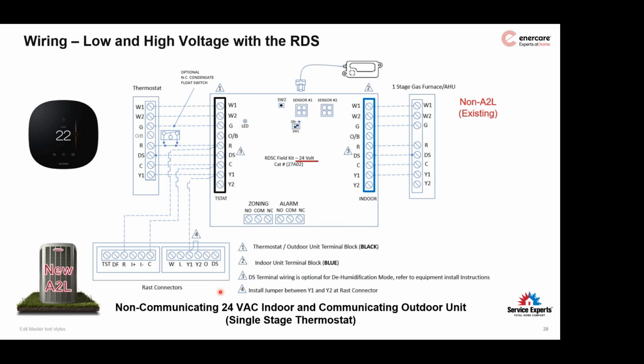If for some reason this was a heat pump, the outdoor unit would also have an O or a B terminal, and then the indoor portion would also have an O or B connection. Again, Lennox specific, we must make sure that we install their O wire, because the control board is making decisions for the blower motor speed and whether it's heat or cooling.